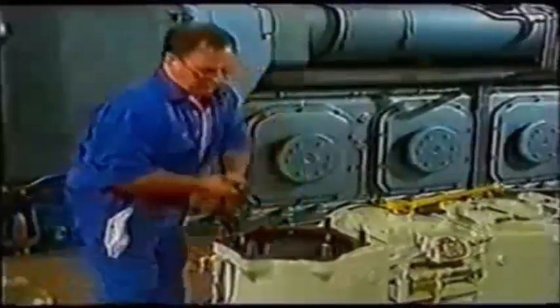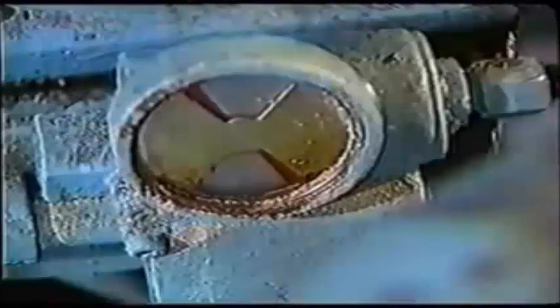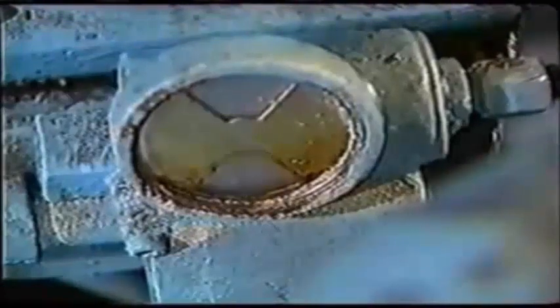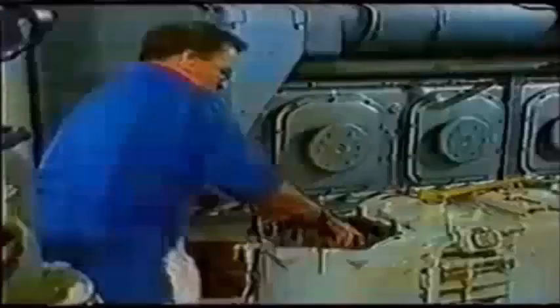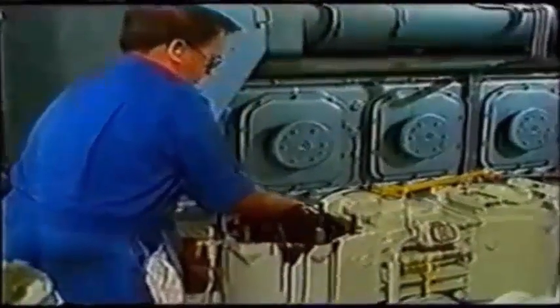Medium-speed installations use back-flushing or self-cleaning filters. Pressure differential between inlet and outlet triggers off back-flushing. If difficulties arise with this type of filter, for instance, frequent back-flushing, the filter elements should be dipped into chemical cleaners which are capable of dissolving and removing hard calcium compound deposits. Or an ultrasonic bath may be used for cleaning them.